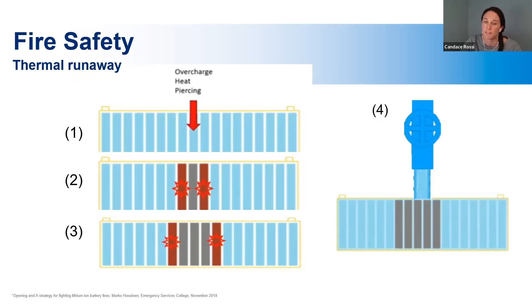So continuing with thermal runaway, this is an example of what it can look like in a module. There could be some kind of event that causes one cell to overcharge and heat, or maybe it's pierced and damaged, and that starts heating up one cell, which spreads to the next and the next. Then, using different mechanisms and suppression systems, it's trying to put out that thermal runaway before it moves on to the next module. So this is the main thing that the code itself is looking to prevent and contain.